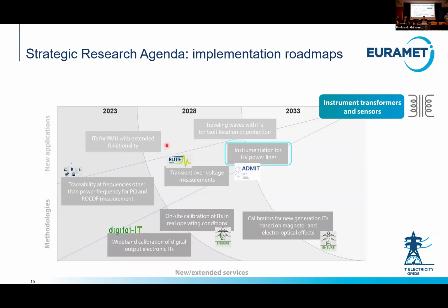This is another area, instrument transformers, that is quite a traditionally metrological domain. As the grid evolves, as the features of the grid change, the frequency of the phenomena change, we need to have fit-for-purpose instrument transformers. And as I was saying before, the instrument transformers generate the data that we then use to make decisions. So we need to trust the instrument transformers, we need to trust the sensors that are on the grid, and we need to make sure that operators use them for the right purposes, because maybe a device was created many years ago for a different purpose and not necessarily suitable for other applications.